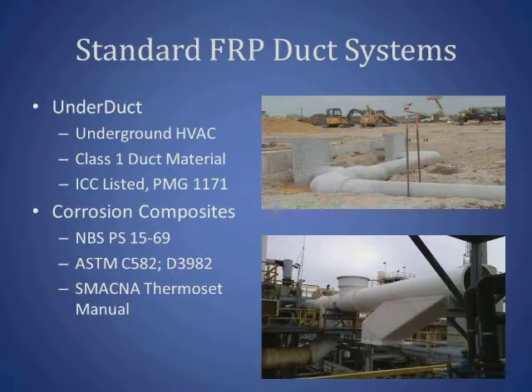Corrosion Composites is the old line, well established by ASTM standards and the original standard NBS PS 15-69, and this is all about wastewater plants, industrial, corrosion-resistant fiberglass. A very well-established market driven by these standards. ASTM C582 and D3982 are the ones that govern duct for the most part. Also, SMACNA has a thermoset manual that covers the corrosion side.